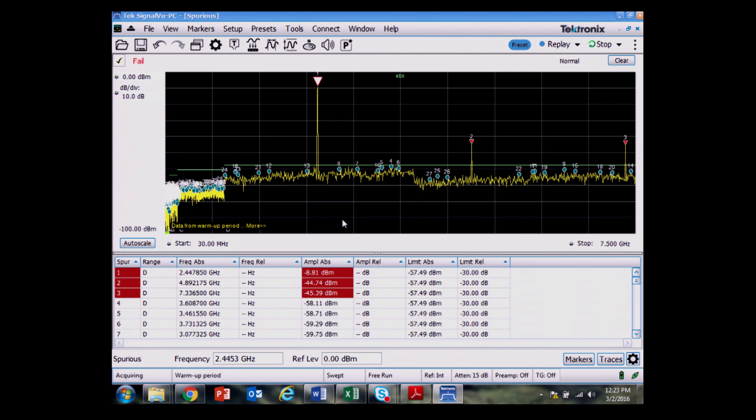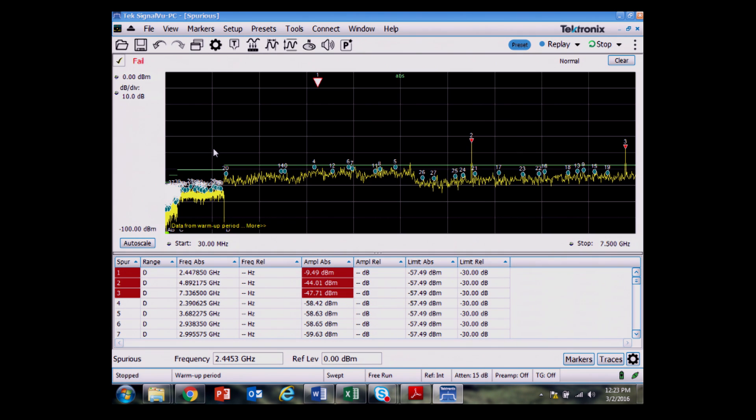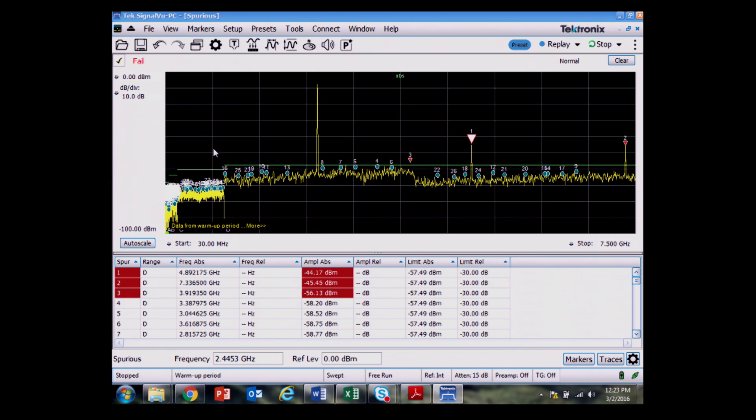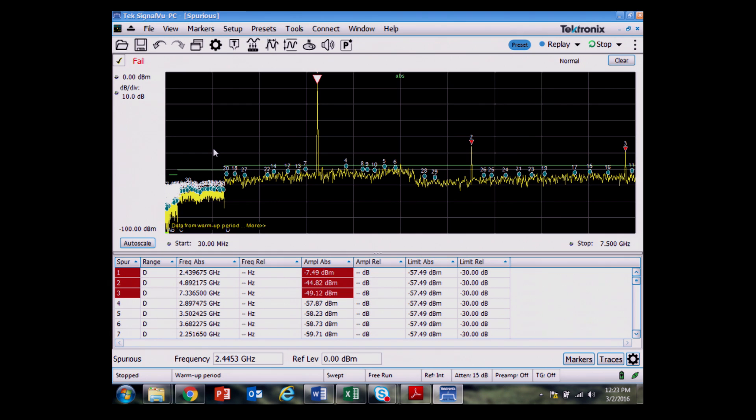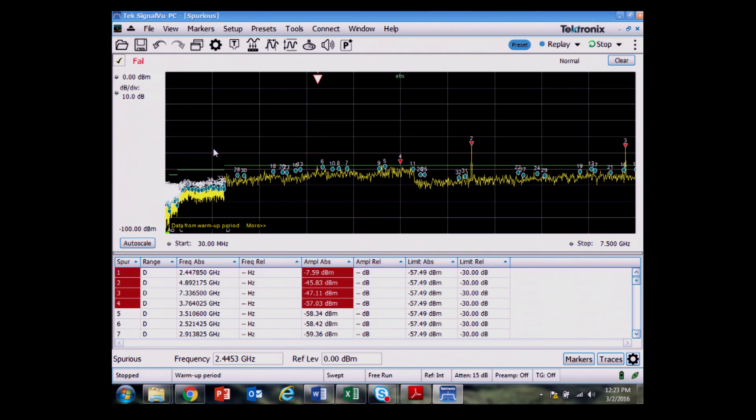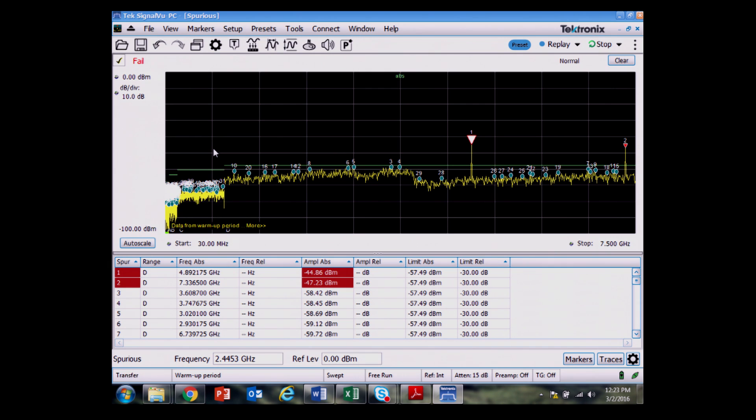Now let's say you do have background noise, maybe from an FM broadcast in the lower portion of the spectrum. The way that you'd discern that is you'd have to do a measurement with the device turned off and then one with the device turned on and disregard the background signals that would be present if you don't happen to have an anechoic chamber or some other way to make a quiet RF environment.